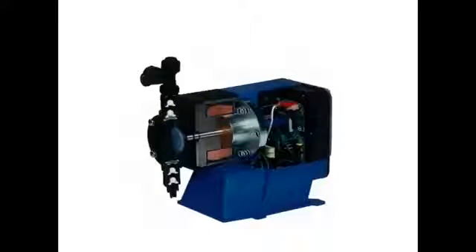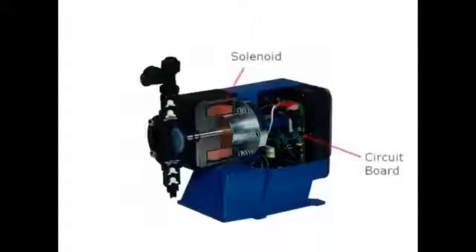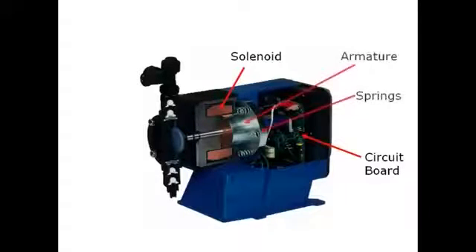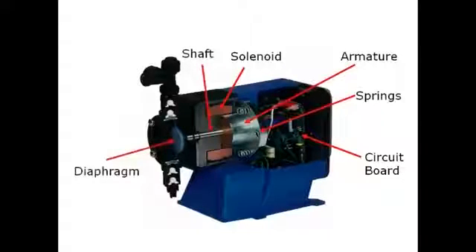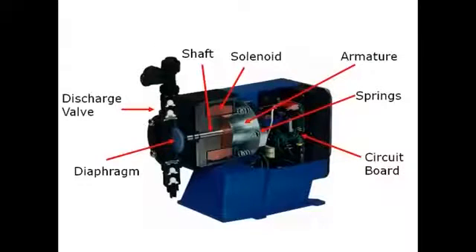The Pulsatron series pump is classified as an electronically driven diaphragm pump. The circuit board supplies a voltage to the solenoid, which generates a magnetic field. This pulls the armature forward against the spring tension. This also pulls the shaft forward, which has a diaphragm connected to it. The diaphragm displaces the fluid in the head through the discharge valve.